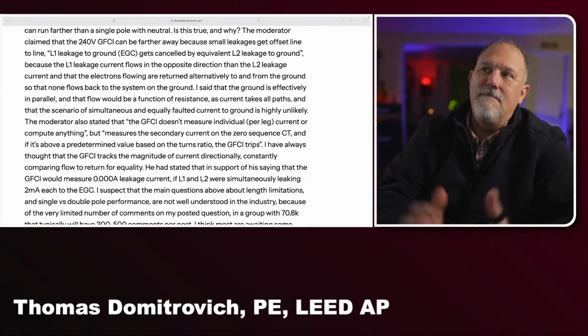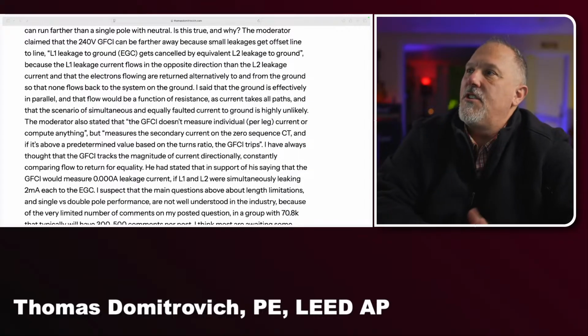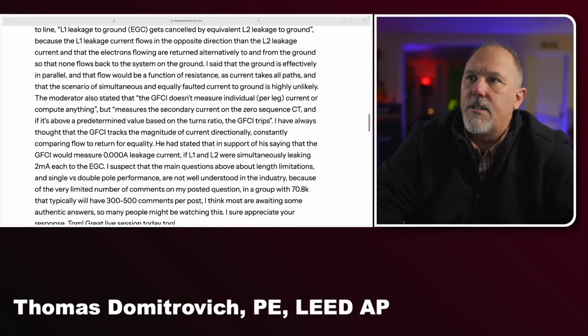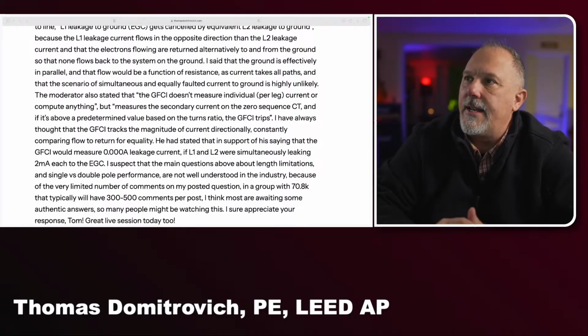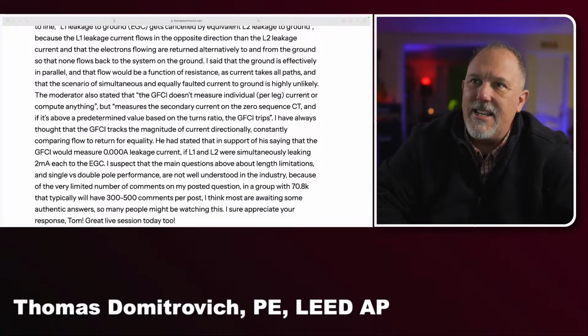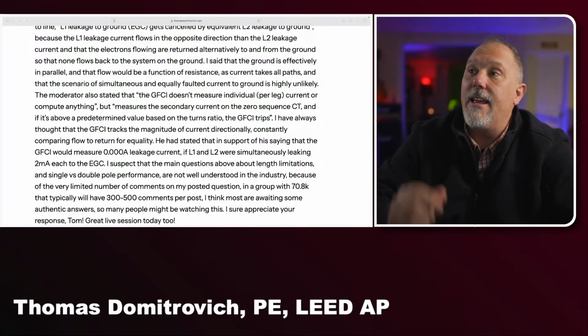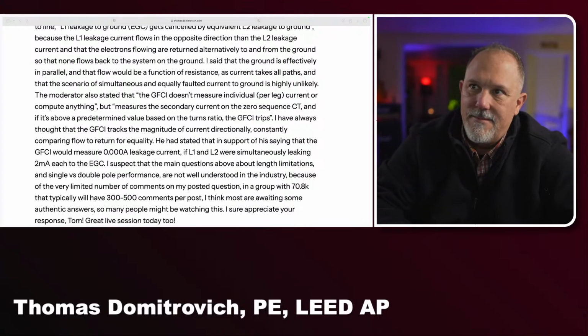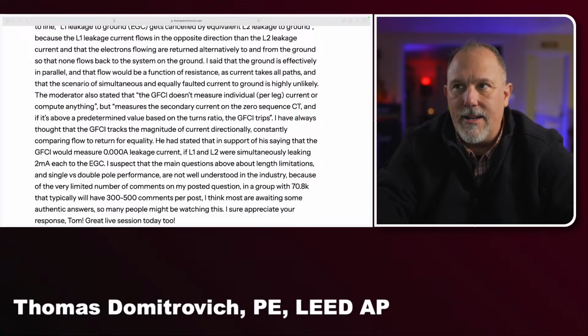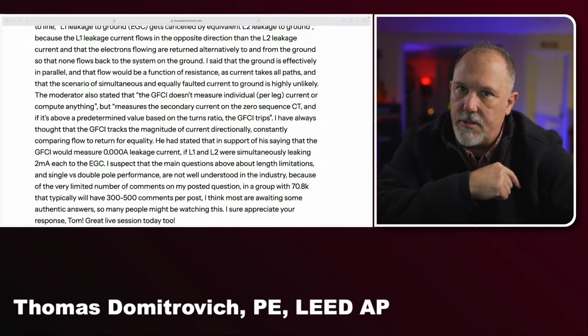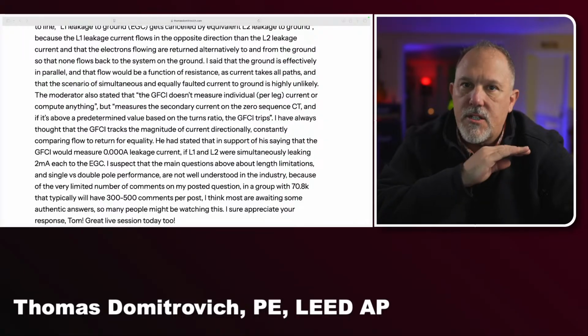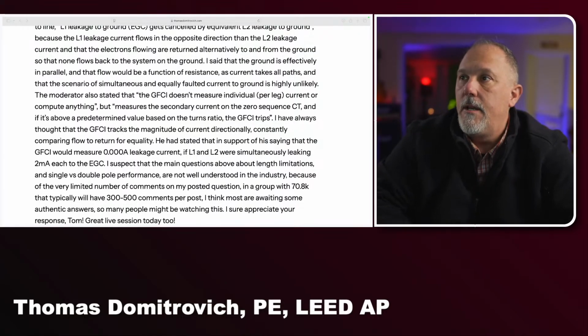I don't know. Anyway, the GFCI doesn't measure individual per leg current. Okay, we read that. I have always thought that he had stated that in support of his saying that the GFCI would measure 0 amps leakage current if L1 and L2 were simultaneously leaking 2 milliamps. If it's leaking current to the equipment grounding conductor, and the equipment grounding conductor is not going through the zero sequence CT, that means the gozaltas aren't equal to the gazintas. It's going to trip.